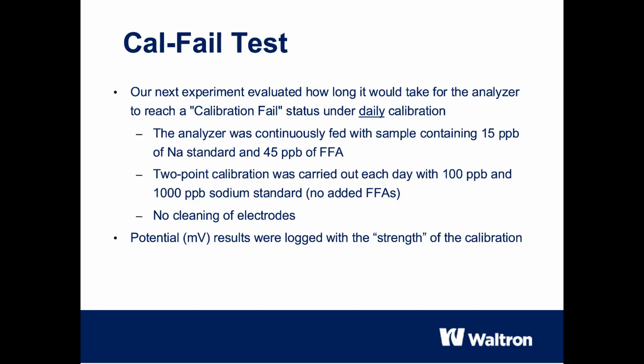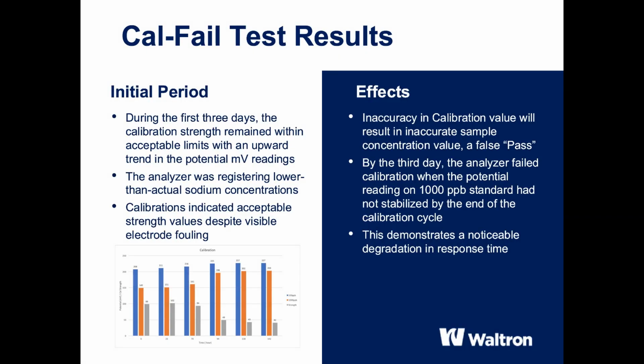We recorded the millivolt potentials and the calibration strength, i.e. the slope of the electrode. The results of this test demonstrate the gradual failure of the system in detail. For the first few days, everything seemed fine. The calibration strength, shown here in gray, remained within acceptable limits. An operator would not suspect any error here.